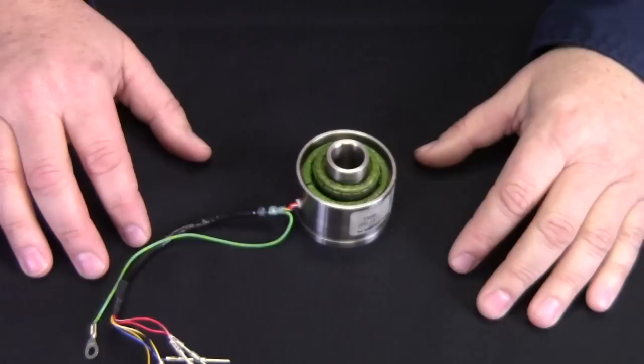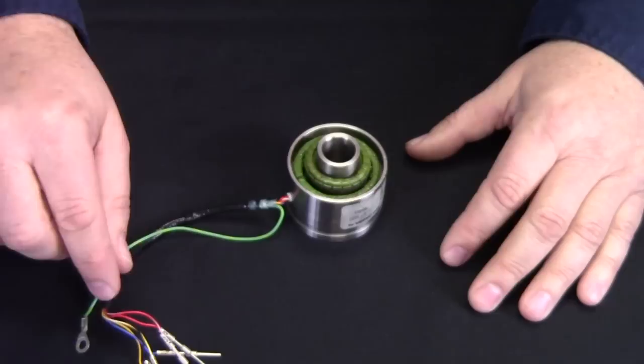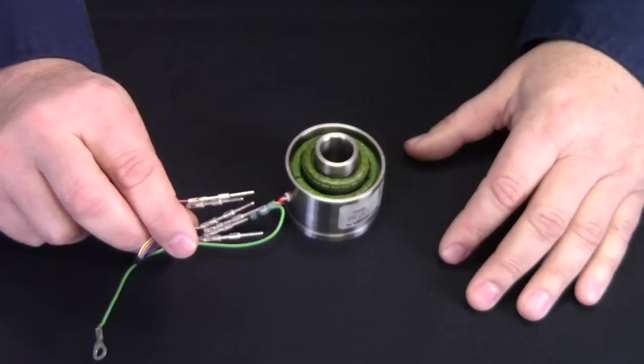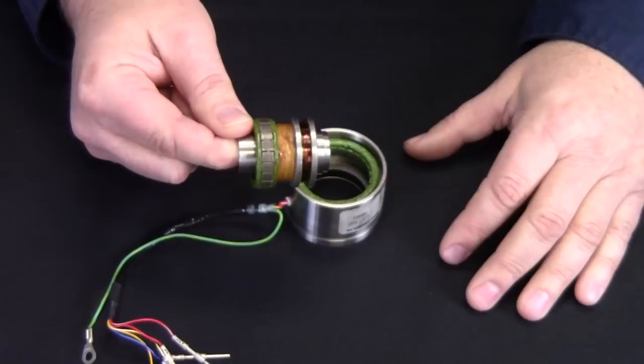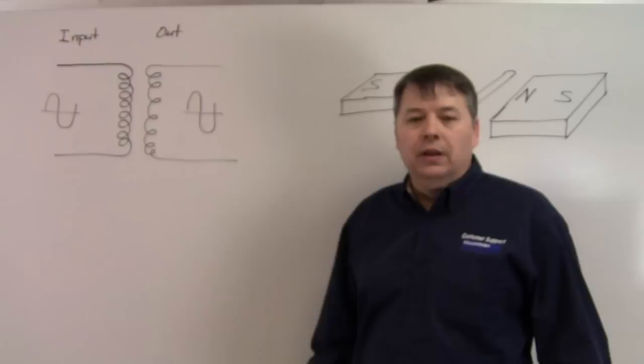A Resolver is made up of two basic components, the stator and the rotor. The stator has three transformers inside: the reference, which is the input, and the sine and cosine, which are the outputs. The rotor couples the reference signal back to the outputs located 90 degrees from each other and is the only part that actually moves.